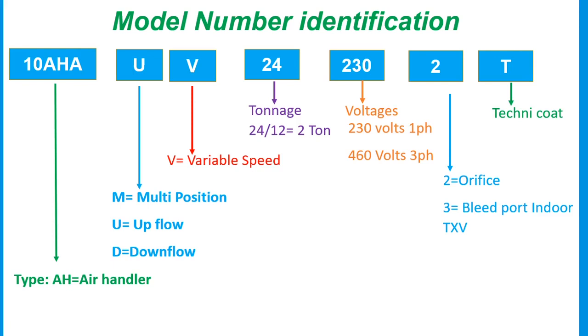Our next topic is model number identification. For example: AH — 'A' is the type, 'H' stands for air handling. 'U' stands for upflow, 'D' stands for downflow. The next letter 'V' stands for variable speed. The number 24 stands for tonnage — from our previous discussion, divide 24 by 12 to get the actual tonnage: 24 divided by 12 equals 2 tons.